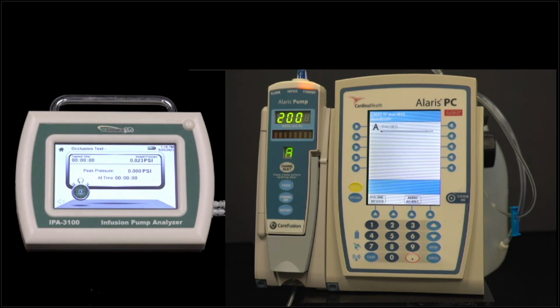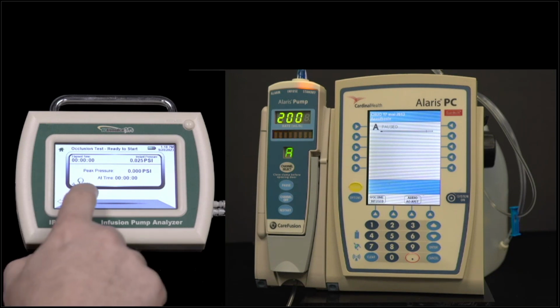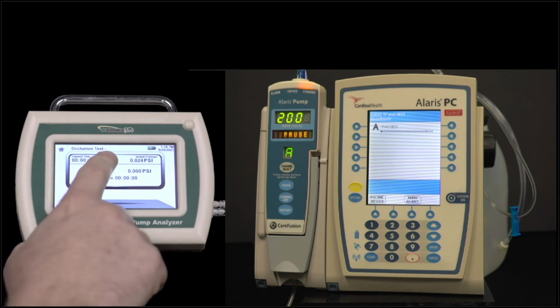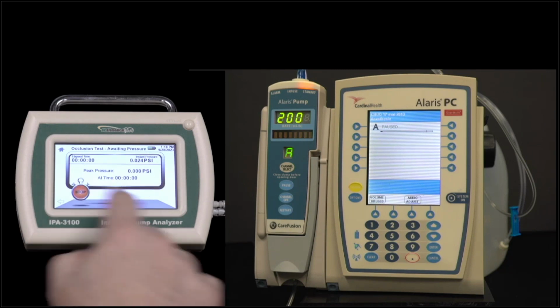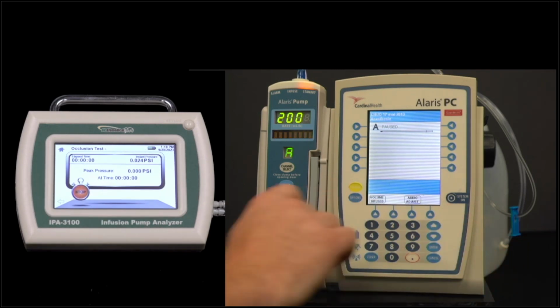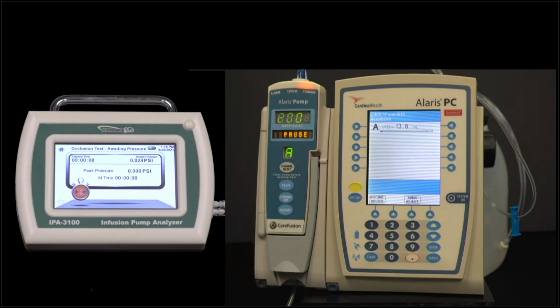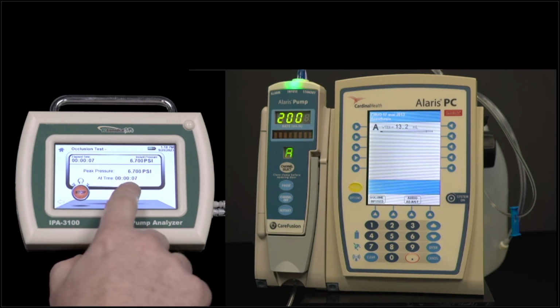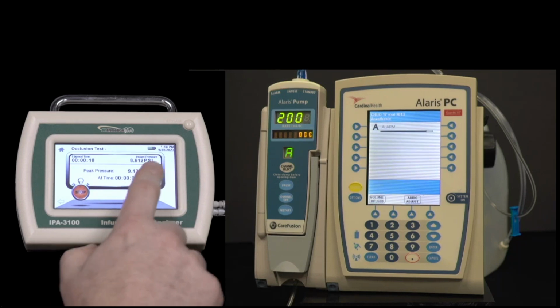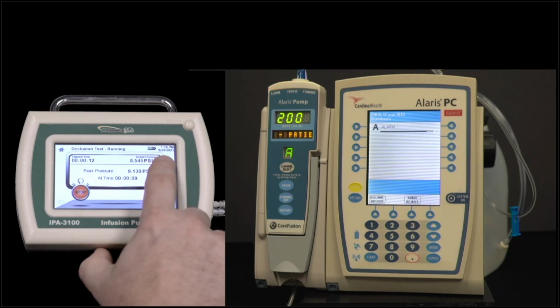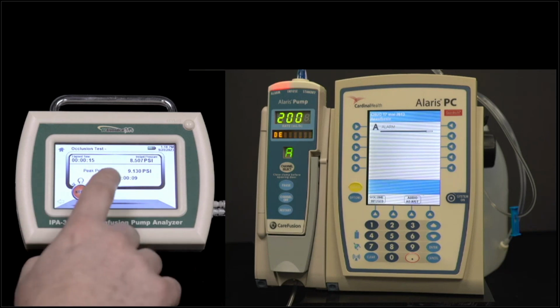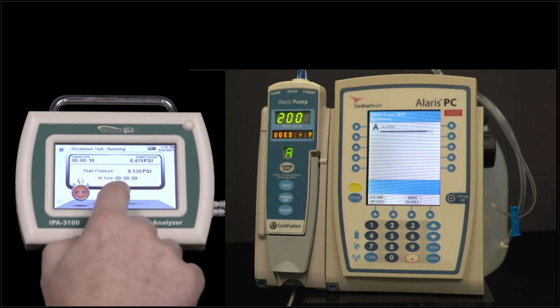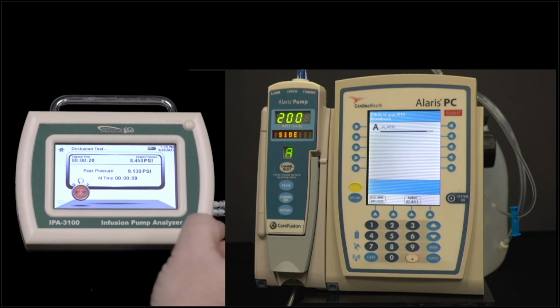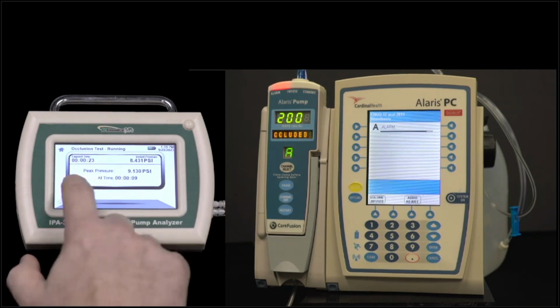So the test, if I run the pump now, it's not going to get any data. I have to start the test, and now it's waiting for the pressure because I had it set to auto. So I'll go in and I'll start, wrong button, restart. There's a lot of buttons on this pump. So we'll go ahead and restart it. We can see the pressure rising, and it's telling us what time the peak pressure occurred. We get a live pressure, so now we can see after it stopped that pressure is dropping a little bit. And we're getting the peak pressure and what time that occurred. We can see that the pump detected that.